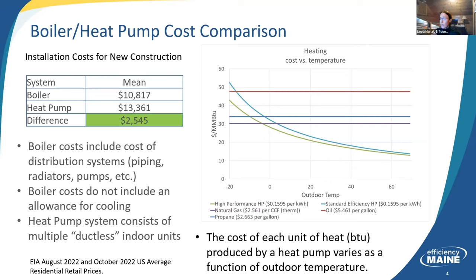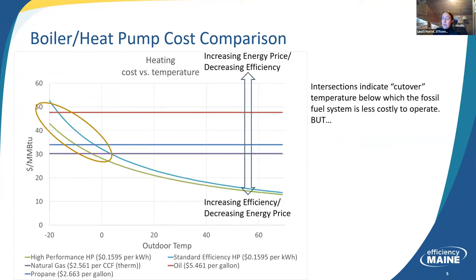Heat pumps are a little bit different. You saw the chart that was shown before that showed that the efficiency of the heat pump drops as the outdoor temperature drops because it's trying to extract heat from colder and colder air. And the colder the air gets outside, the harder it is to extract that heat. That causes the coefficient of performance to go down, which means that it costs more. You have to use more electricity to produce the same amount of heat at those colder temperatures. And that's what creates these curves. And I would draw your attention to the intersections of those curves with the horizontal lines. Each one of those intersections is the point at which the outdoor temperature, which is the x-axis, at which the heat pump below that costs more to operate than the comparative system. And above that, the heat pump costs less.